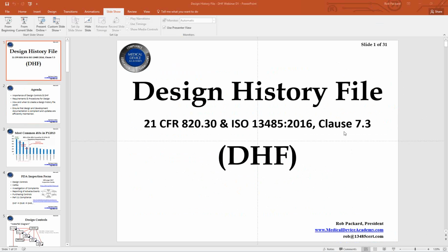So no, you don't have to do full-blown design controls. You don't need necessarily a design independent reviewer. You probably wouldn't even open up a new DHF. You would document it as a design change instead. Somebody liked my answer, so that's good.